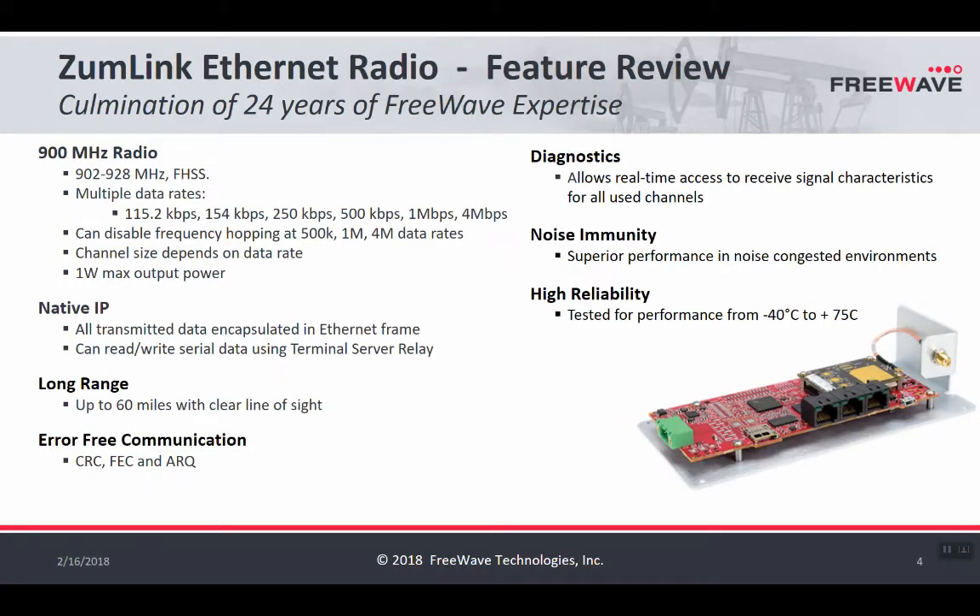Here's an overview of the ZumLink Ethernet radio. This is a project that's been 24 years in the making, and it continues on the success of the 900 megahertz FreeWave radios that are well known and well-loved. It is an unlicensed radio in the 902 to 928 band. There are multiple data rates available, which is a big advantage over FreeWave's traditional Ethernet radios, offering more granularity in adjusting speed versus distance. In traditional FreeWave Ethernet products there are only two RF data rates, whereas ZumLink has many RF data rates.